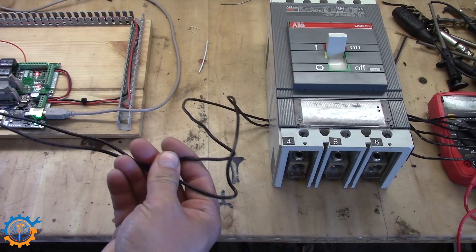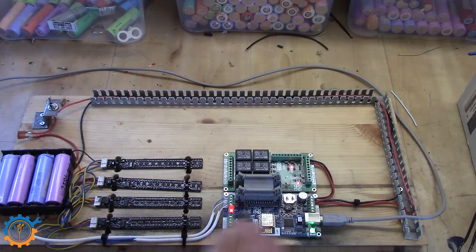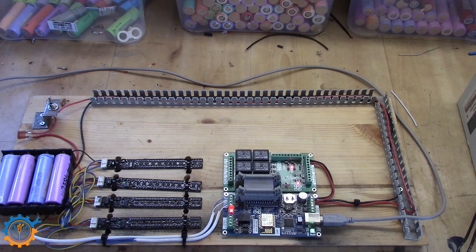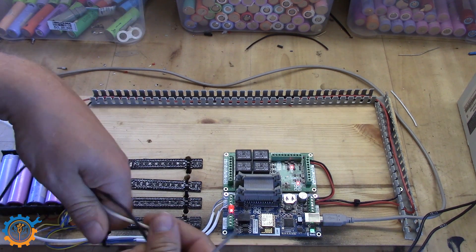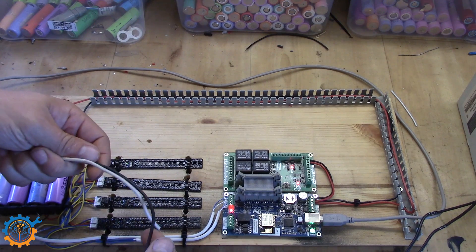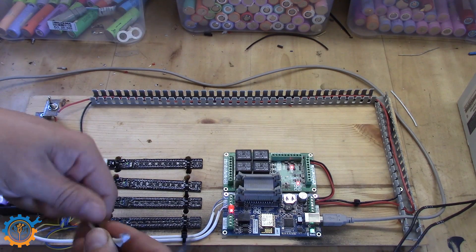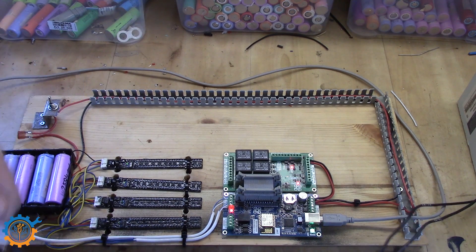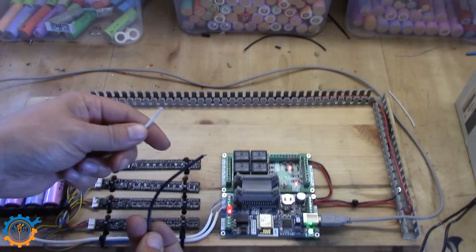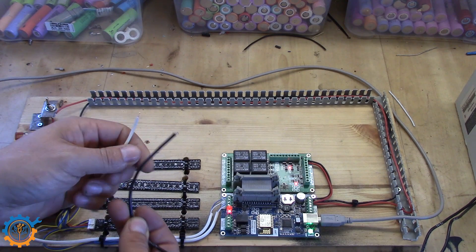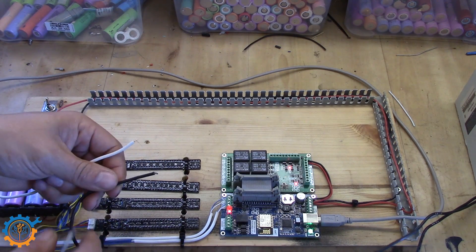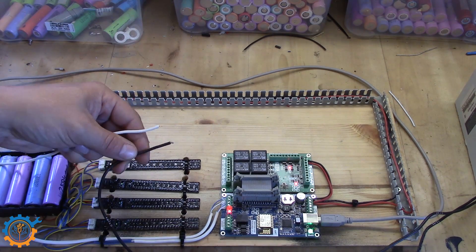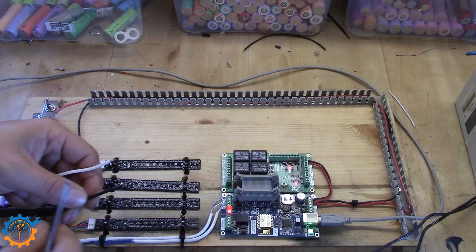We need to get power into those cables here. Since I don't have 24 volt on this setup here, I have brought in these two wires here that are hooked up to my power supply and will be supplying 24 volt. One of them are directly hooked up to the shunt trip. And the other one and including the shunt trip wire will be hooked up into the expansion board. And this is to be able to make a continuous loop and the power will go through when the relay is pulled.